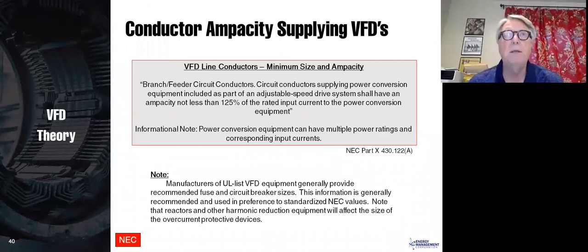Now, we typically recommend setting the overload protection of the drive at 100% of the full load amps. So I really think this doesn't make total sense, but I certainly understand that they're trying to be safe. The drive could have a bypass in it. You never know if somebody could take the drive out. And so that remains a requirement that the output cable needs to be rated for 125% of the motor amps, from the motor to the VFD.